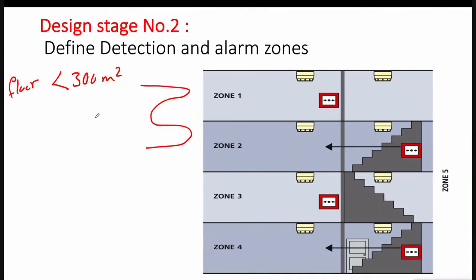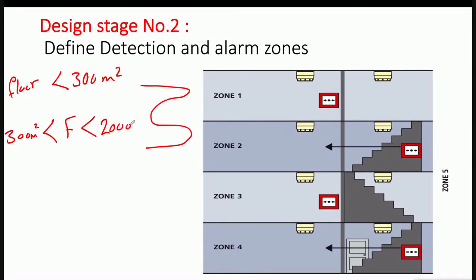If a floor is less than 300 square meters, you can assign the zone to more than one floor. But if a floor's area is bigger than 300 square meters and less than 2,000 square meters, you should assign a separate loop or a separate zone for each floor.